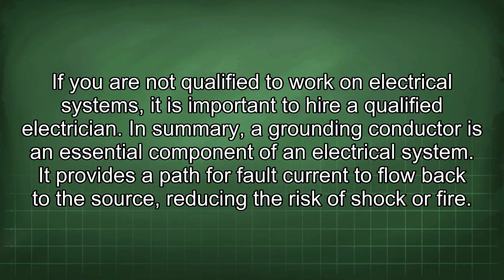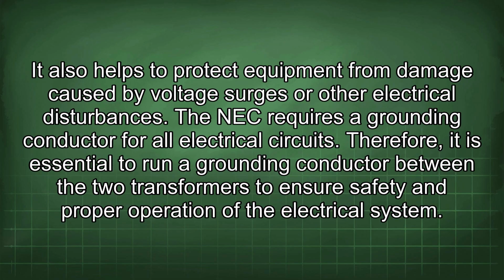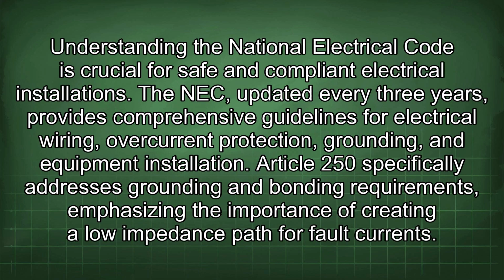In summary, a grounding conductor is an essential component of an electrical system. It provides a path for fault current to flow back to the source, reducing the risk of shock or fire. It also helps to protect equipment from damage caused by voltage surges or other electrical disturbances. The NEC requires a grounding conductor for all electrical circuits. Therefore, it is essential to run a grounding conductor between the two transformers to ensure safety and proper operation of the electrical system. Understanding the National Electrical Code is crucial for safe and compliant electrical installations.